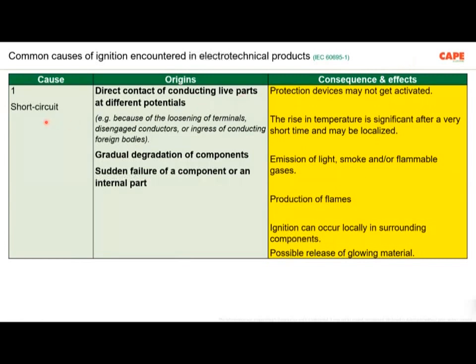So the first cause of electrical fire is short circuit. Why does it happen? It is happening because of a direct contact of conducting live parts at different potentials. So your conductors, your wires are having different voltages, and due to an insulation degradation or insulation failure, if these two wires are in touch, of course you get a short circuit.